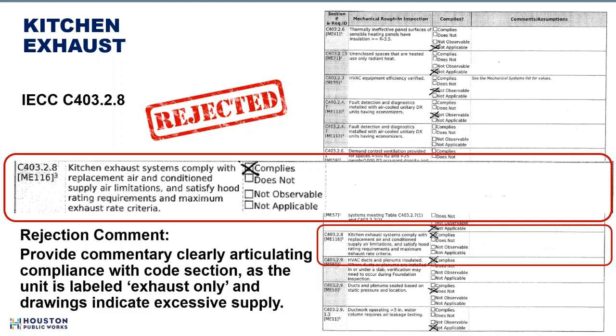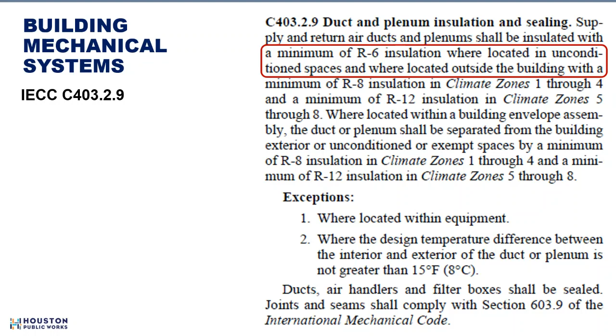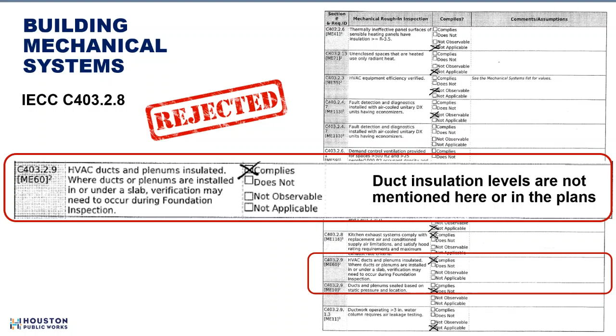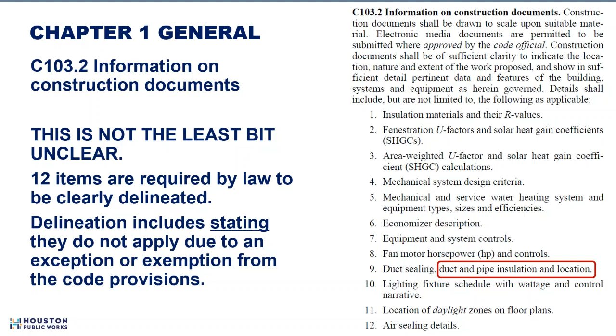Here's another quick one, just looking at provisions. Duct and plenum insulation, we need R6 insulation, etc. And so we would look on the inspection checklist, find that provision about the insulation of ducts and plenums, and, as you can see, no comment. So duct insulation levels are not mentioned here or on the plan, so that would be a rejection, in spite of the engineer saying it complies. The fact that you say it complies or will be met is not going to get it. All right, back to the 12 items. Look at that: duct sealing, duct and pipe insulation, and location required on the drawings.